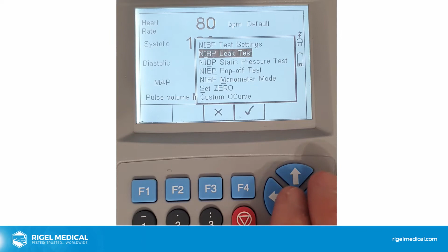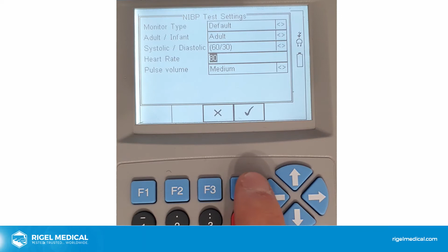NIBP test settings. Then we've got a series of other NIBP tests which I went through in the webinar. Your leak test, static pressure, pop-off tests. So you can do these manually as well, but we're only interested in the test settings. Default adult 120/80. We'll put 60/30 just to throw in an anomaly on this test, just as an example. Keep the heart rate at 80. That's fine. Then we hit the home button, and as you can see, all the test settings are there on screen. Now to perform the simulation, all we've got to do is hit the green button.